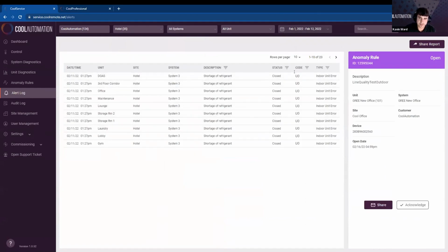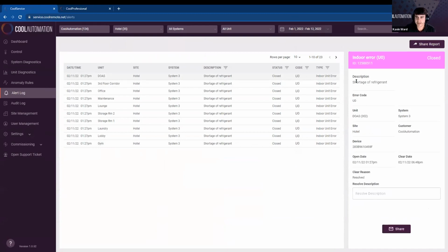And we can see that there was a U0 error code. By clicking on this, you get a description. The U0 error code is translated as a shortage of refrigerant. So we know that there's absolutely an issue on February 11th. You can see this affected all of system 3.